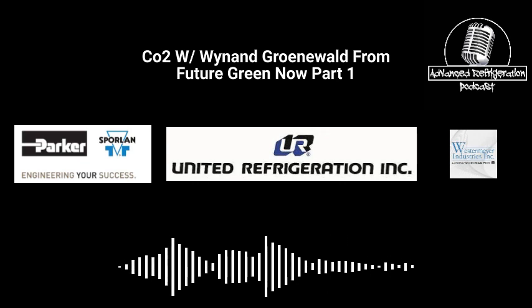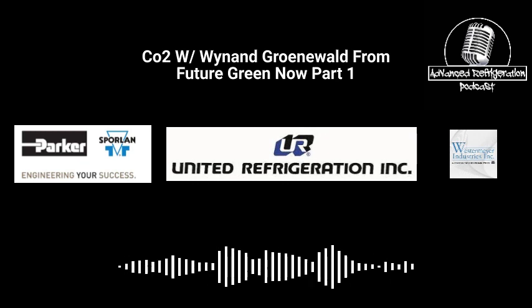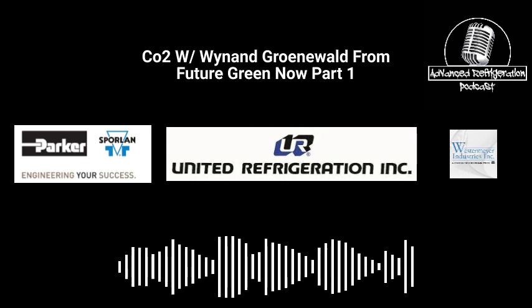So it's two things I want to bring up. We have one manufacturer that tried that, and it's working. They're bypassing the gas cooler and injecting right into the flash tank, and it seems to be working. These racks have very little load. We float them from running a plus 18 SST to, on one of them, a plus 26. But we start hitting that threshold where the flash tank is running at plus 33 or plus 34, and we don't have that pressure differential.